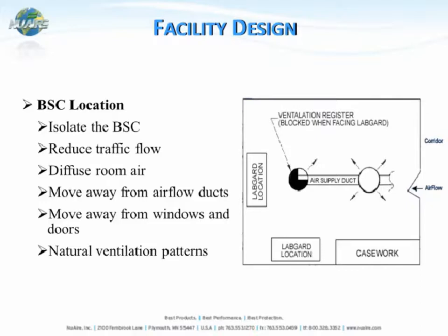If ventilation registers are blowing air directly at the unit, it could affect the performance of the cabinet, which in turn could mean it doesn't appropriately protect the product, the personnel, or the environment as it should.